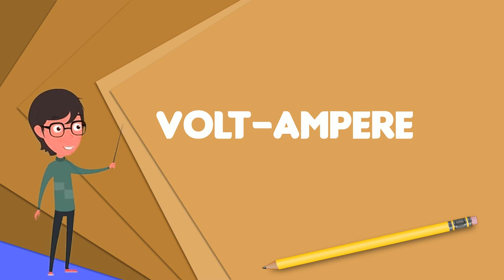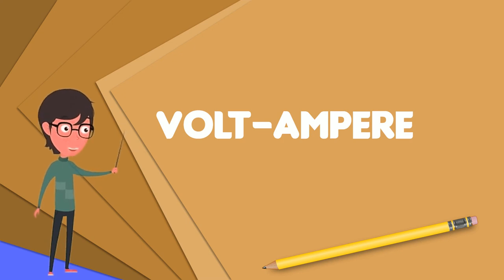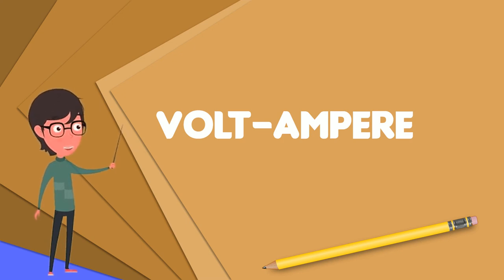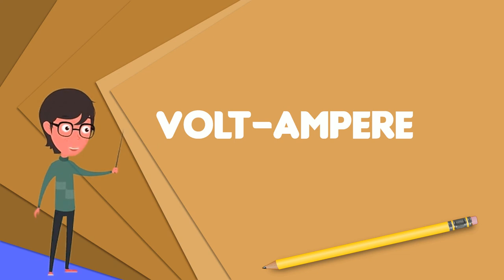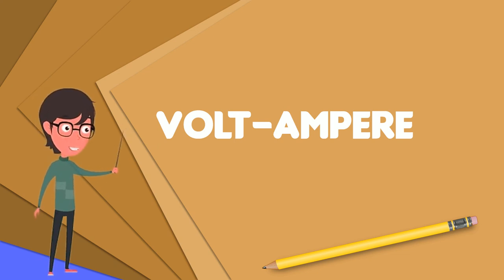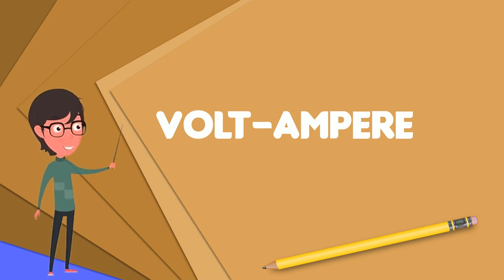VA ratings are also often used for transformers. Maximum output current is then the VA rating divided by the nominal output voltage. Transformers with the same sized core usually have the same VA rating. The convention of using the volt-ampere to distinguish apparent power from real power is allowed by the SI standard.